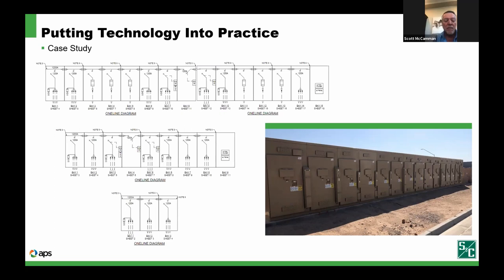And so we went to the adjacent manhole, and we were able to first manipulate the switches so the first customer could be on that temporary feeder as well as the second customer, since the second customer's initial load wasn't their 20 MVA. Then we were able to go to the adjacent manhole and route the first feeder in and out of that 9-bay. Then we were able to do a closed transition and get the first customer back on their initial feeder, which also allowed for the third customer to be fed out of this 9-bay on that same feeder.